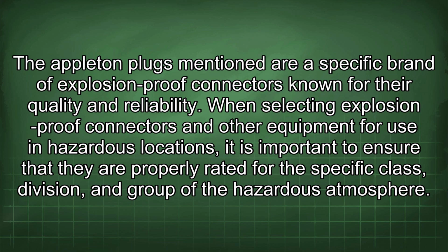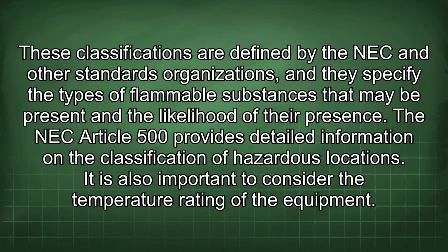When selecting explosion-proof connectors and other equipment for use in hazardous locations, it is important to ensure that they are properly rated for the specific class, division, and group of the hazardous atmosphere. These classifications are defined by the NEC and other standards organizations, and they specify the types of flammable substances that may be present and the likelihood of their presence. The NEC Article 500 provides detailed information on the classification of hazardous locations.